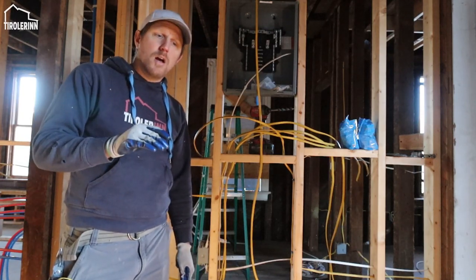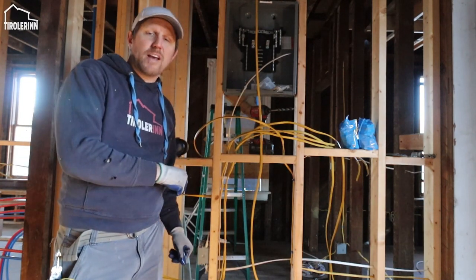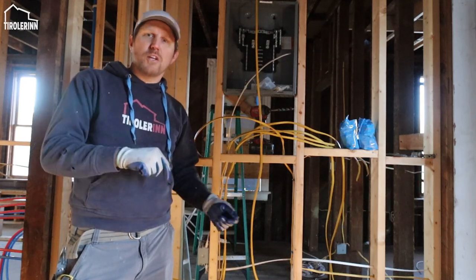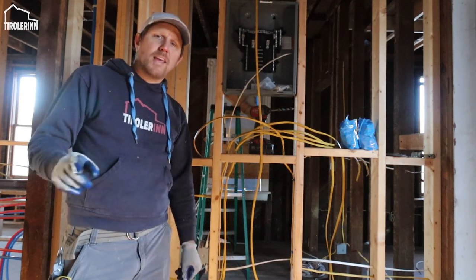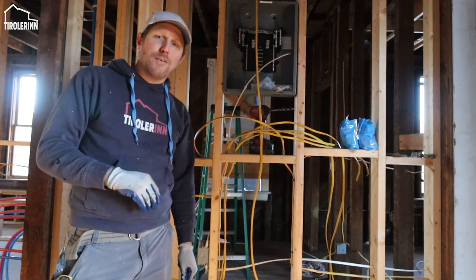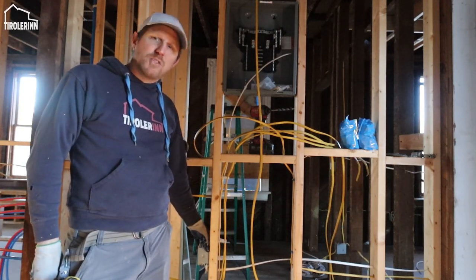circuit that is fed through one box that I have that just connects everything into it. Reason why I do that is, you might say, oh, but there's way too much overload. Yeah, if I would do traditional lighting, yes, but since everything is gonna be powered with LEDs, all my cans really just draw somewhere between 8 and 12 watts. The amount of wattage that I will have in that entire box is so low that I wouldn't even theoretically need a full 15 amp circuit for it.